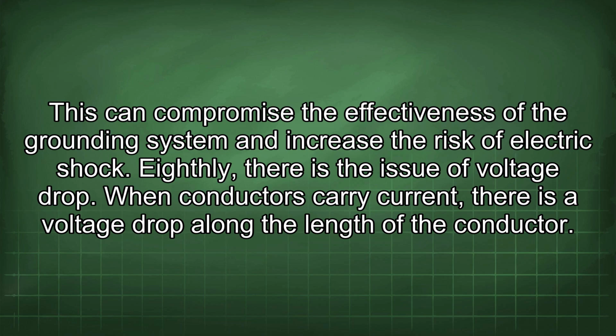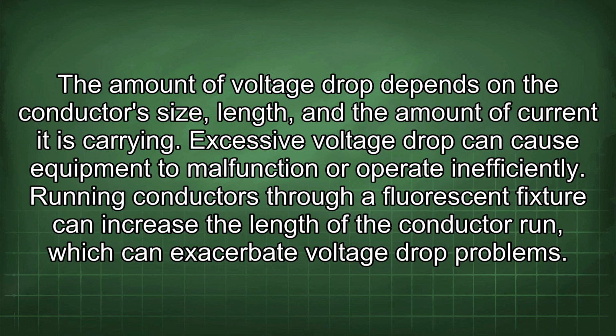Eighthly, there is the issue of voltage drop. When conductors carry current, there is a voltage drop along the length of the conductor. The amount of voltage drop depends on the conductor's size, length, and the amount of current it is carrying. Excessive voltage drop can cause equipment to malfunction or operate inefficiently. Running conductors through a fluorescent fixture can increase the length of the conductor run, which can exacerbate voltage drop problems.